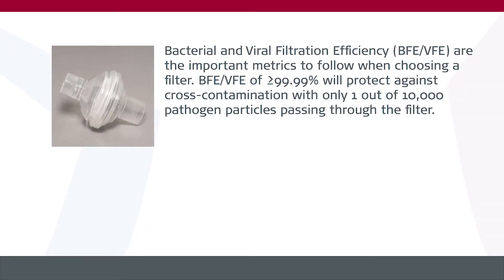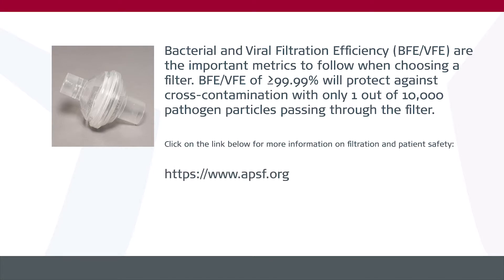There are two key performance measures that filters must meet to be effective. The first is bacterial filtration efficiency, or BFE, and the second is viral filtration efficiency, or VFE. The efficiency of a filter is measured in terms of percentage of pathogens that are blocked or captured by the filter material. A VFE of 99.99% means only one particle — a virus or bacteria — in 10,000 will pass through the filter under standard testing conditions. Since the COVID-19 pathogen is a virus, the focus of filtration conversations recently has been on viral filtration efficiency. Current recommendations are to use a filter with a VFE of 99.99%. The Anesthesia Patient Safety Foundation and American Society of Anesthesiologists have some good web pages on recommendations for filtration devices.